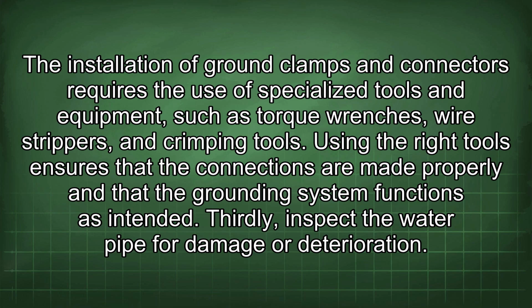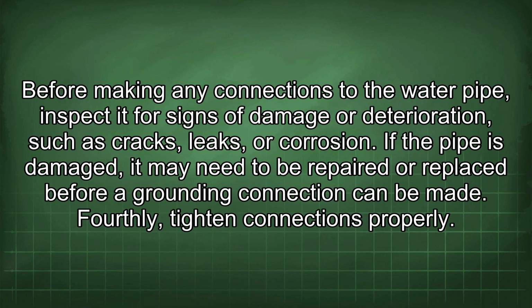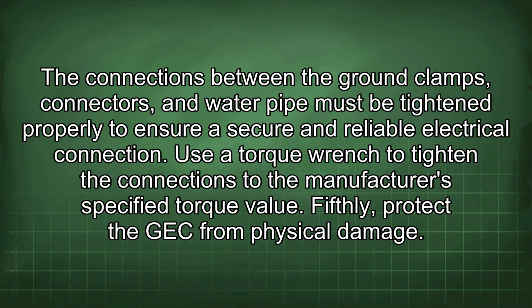functions as intended. Thirdly, inspect the water pipe for damage or deterioration. Before making any connections to the water pipe, inspect it for signs of damage or deterioration, such as cracks, leaks, or corrosion. If the pipe is damaged, it may need to be repaired or replaced before a grounding connection can be made. Fourthly, tighten connections properly. The connections between the ground clamps, connectors, and water pipe must be tightened properly to ensure a secure and reliable electrical connection. Use a torque wrench to tighten the connections to the manufacturer's specified torque value.